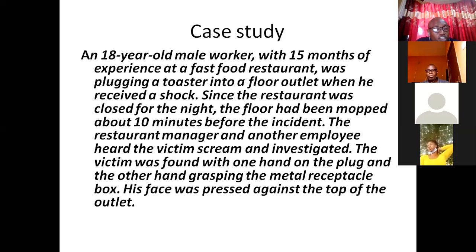I gave a case study of an 18-year-old male worker with 15 months of experience at a fast food restaurant, and he was plugging a toaster into a floor outlet when he received a shock. The restaurant floor was mopped 10 minutes before, and he wants to plug the toaster into an outlet on the floor that was just mopped.